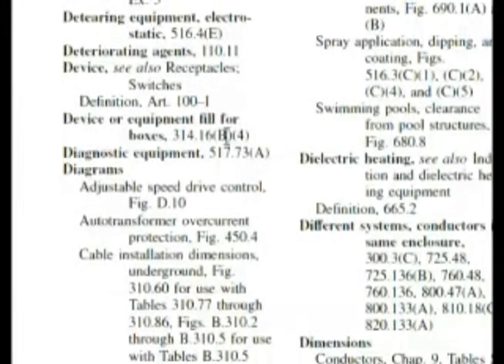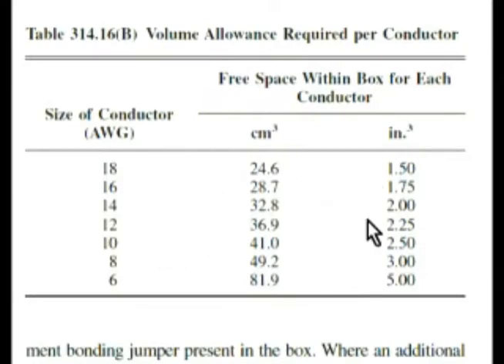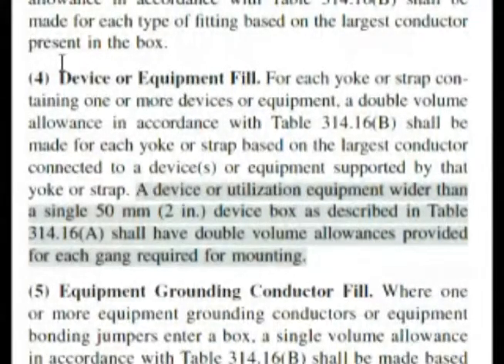So we'll go to section 314.16B4. But when we get there, I want to go to the table first and show you something. Here's our table 314.16B — volume allowance required per conductor. But does this help us find our answer? The question was about each strap containing one or more devices counting as blank volume allowance. The table talks about the size of a wire in that box, but what does this have to do with our device? We would have gone down the wrong place. 314.16B4 is what we found in the index, so let's go there right now.